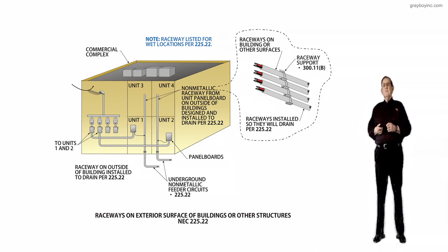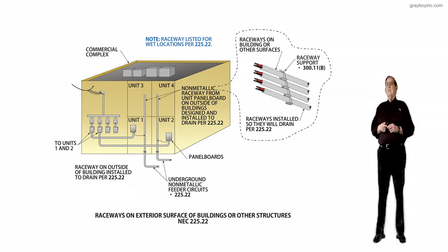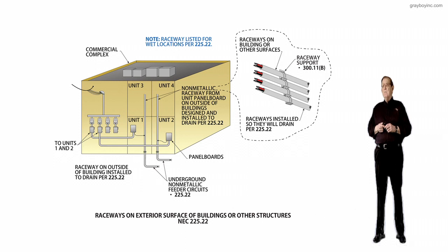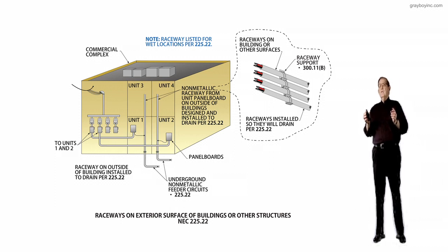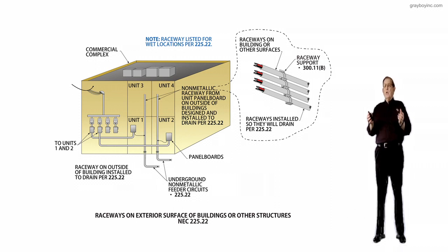Now, to review this then, notice the illustration to the right that shows these raceways. We could go to 300.17, the informational note, and all of your different raceways, conduits, and so forth are listed in the 300.17 informational note. But if we're reviewing, say, a cable tray system, it's not listed there. We have to go to 392.2 to pick up a cable tray, and it's really just a supporting means for cables and conductors and so forth.